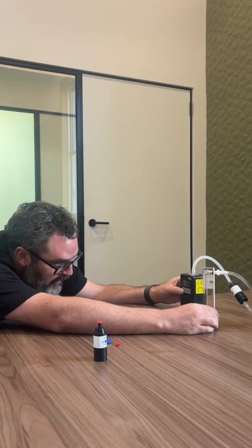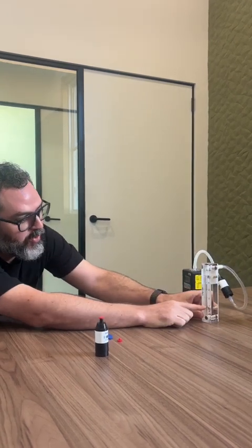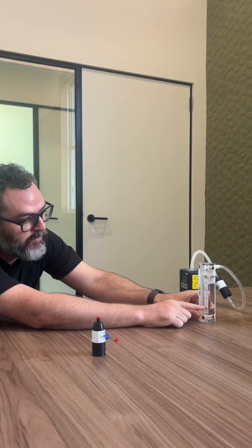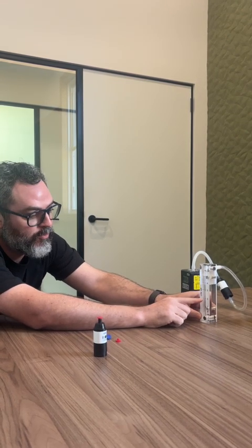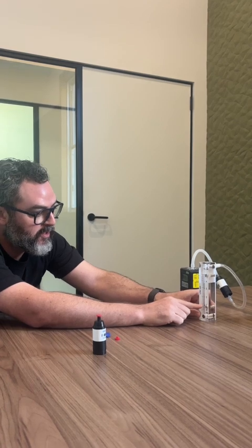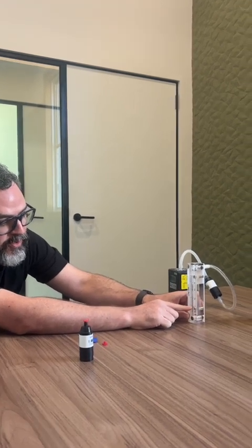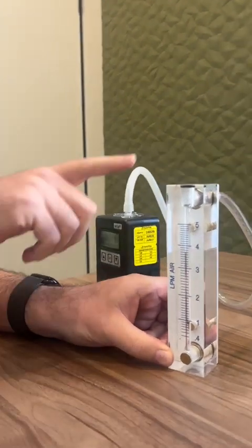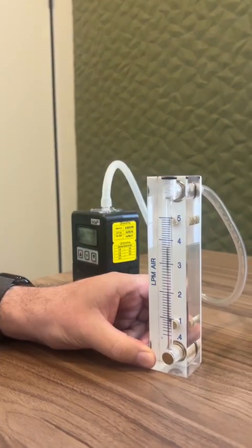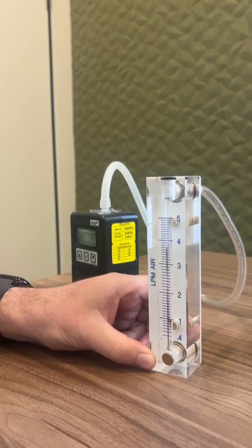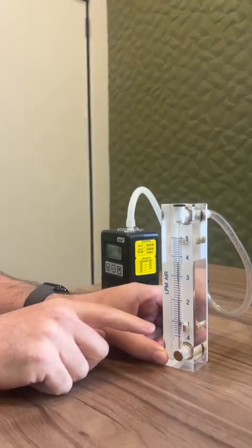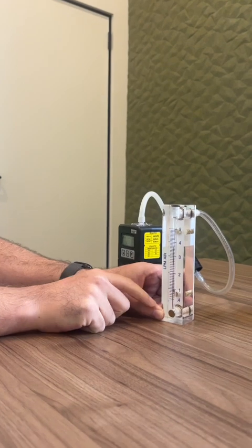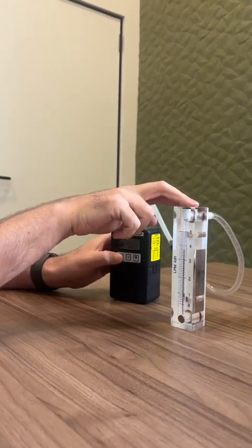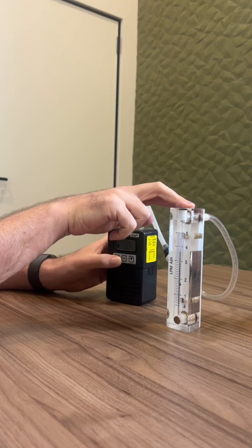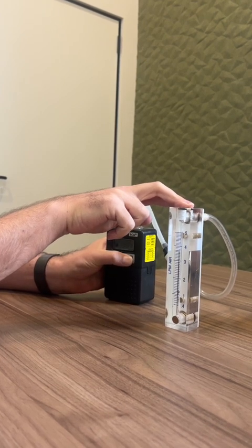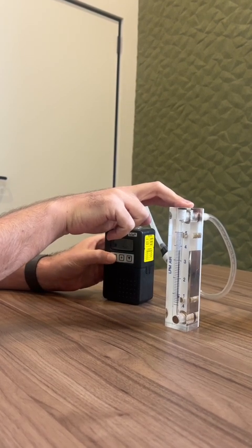on the pump. Now we need to make sure that the ball sits level with whatever our selected flow rate is. So this is going to be for an 8-hour shift, so we're going to set it to 1. So this ball should be sitting, the middle of the ball should be bisecting level 1. So the top of the ball will be just above it and the bottom of the ball will be just below it. If we need to adjust it, we're pressing up and down on the pump until we get that to sit where we need it.